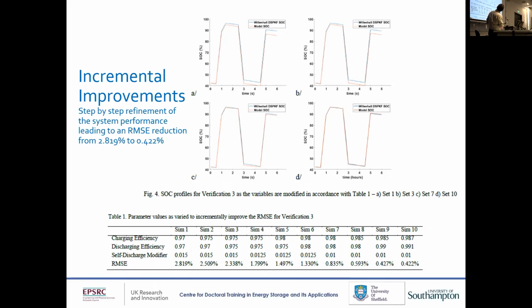As we changed it, going from B to C and finally D, that's simulation 10, we ended up with an RMSE of 0.422%, which is a lot more accurate. What we were trying to do is figure out empirically how the Willenhall battery performs now, since it's been operating for years and its charging efficiency, discharging efficiency, and self-discharge characteristics have changed. So that's probably the best estimation we could have got.